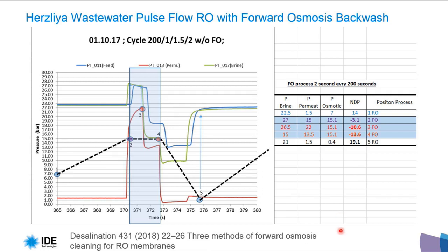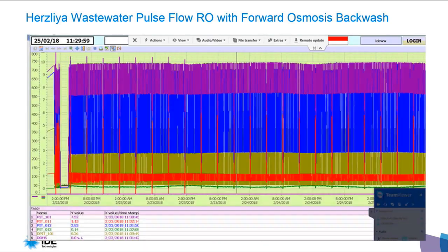Periodically, we perform forward osmosis backwash — moving water from the permeate side to the feed side. We do this every three hours for five minutes under this water condition, but it must be adjusted for each water condition. You can read about it in the journal Desalination, volume 431, this year.